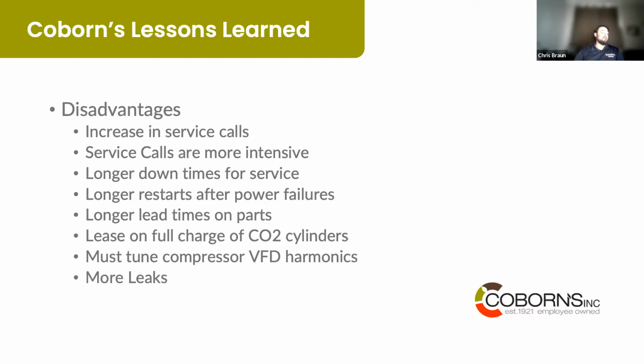After power failures, typically if you have a 2-hour power failure, power comes back on, you start that system up in 30 minutes and you're back up and running. We are seeing that you do have to stage these things on. You have to bring case controllers on in blocks. So a 2-hour power outage could turn out to be 4 hours, if you're on a large system, before your last system starts staging on.